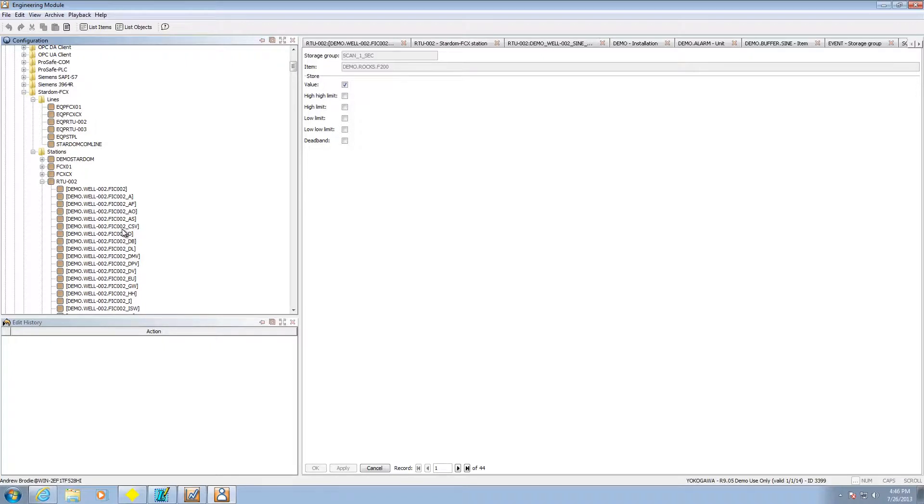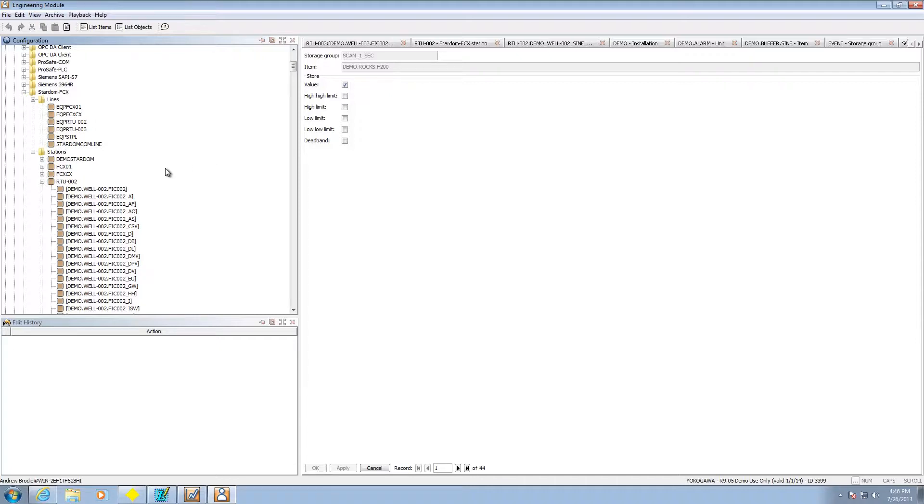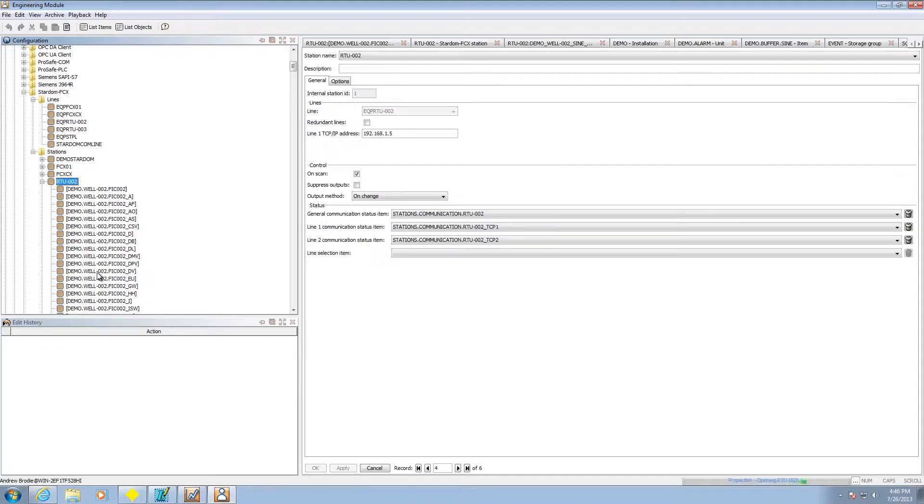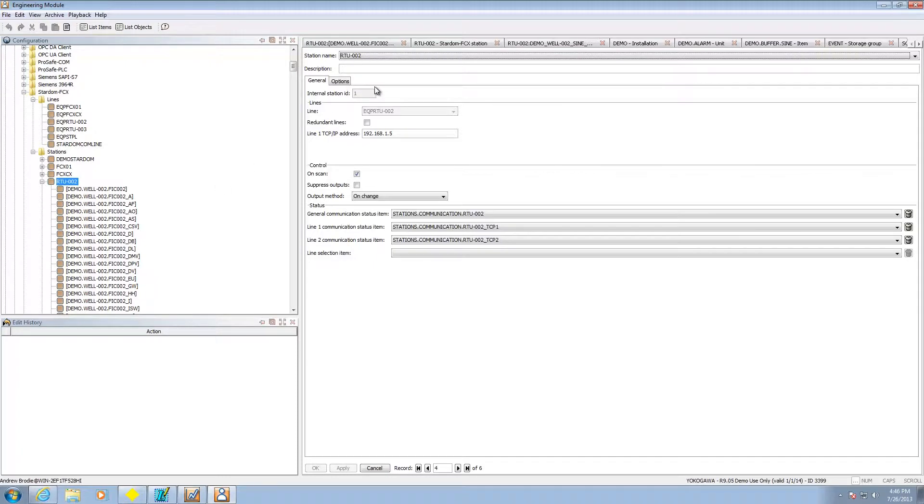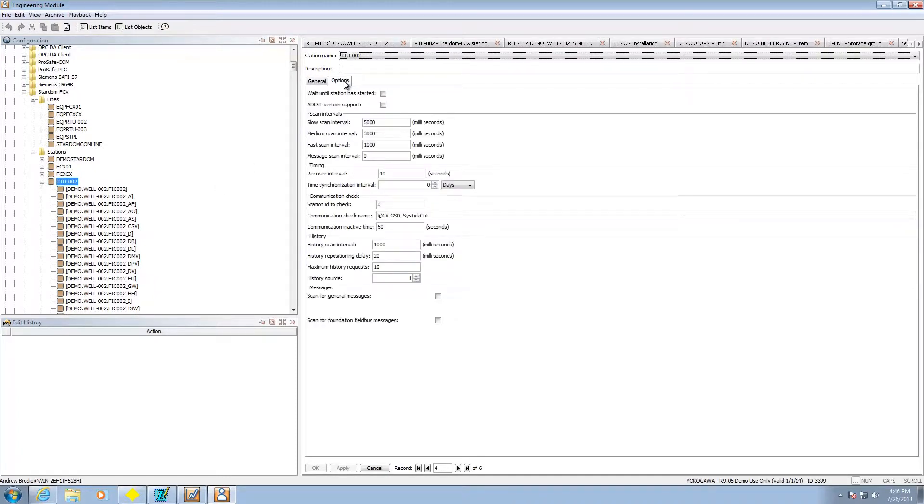Now one of the things that's critical to data logging is knowing how fast you're going to be pulling the data out on the instrument. Let me show you where that's set up. Under the particular station if I look at properties here, if I go under options you're going to see the scan intervals. There's slow, medium and fast.